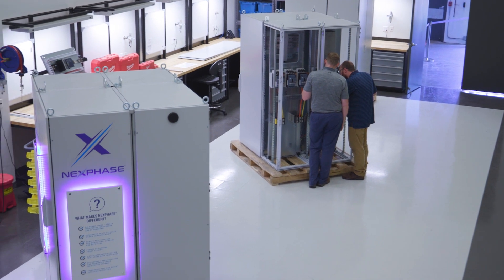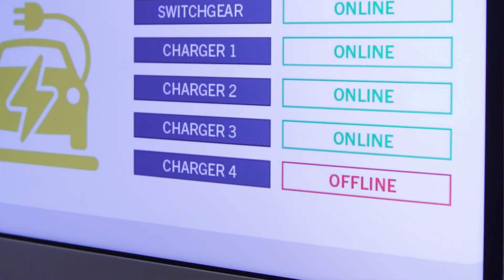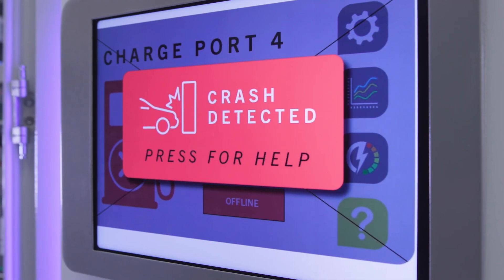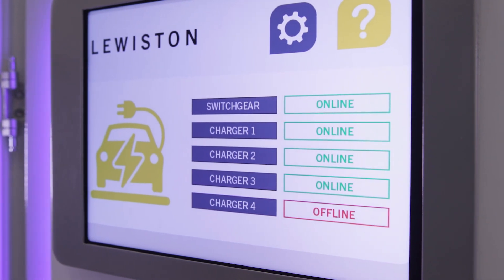NEXPHASE has a number of safety features incorporated into it. If the charging unit was hit, we can receive input from a tilt sensor on a charger and shut down the chargers. We also have an emergency stop input, so if someone hits an e-stop button like you'd typically see at a gas station, it will turn off the chargers. And we have an input for a vapor sensor — if we detect a hydrocarbon, we can turn off the chargers.